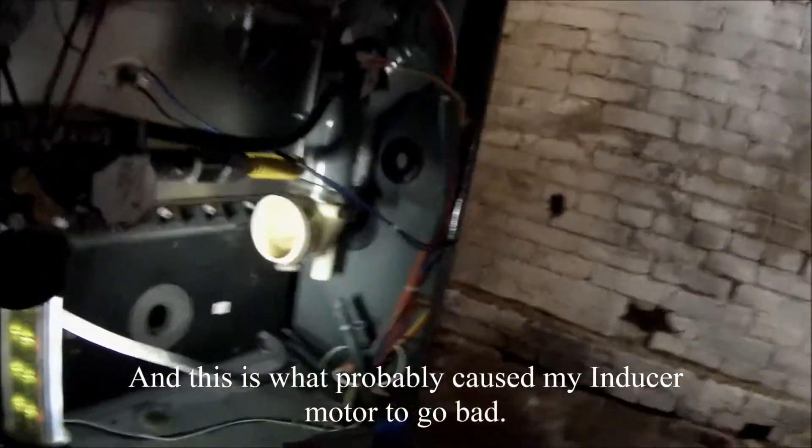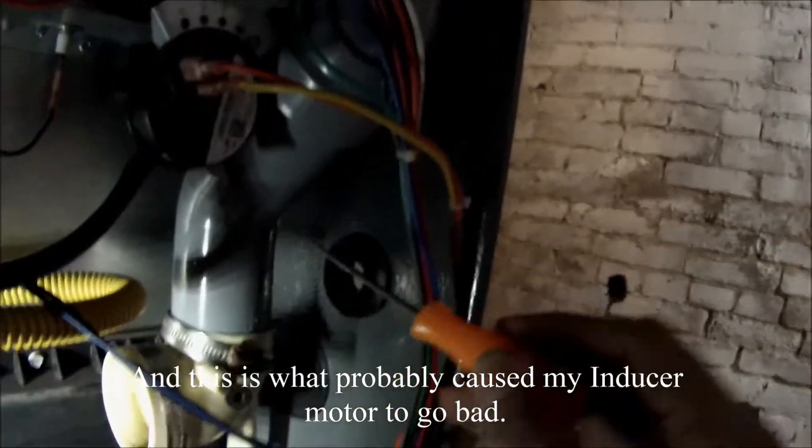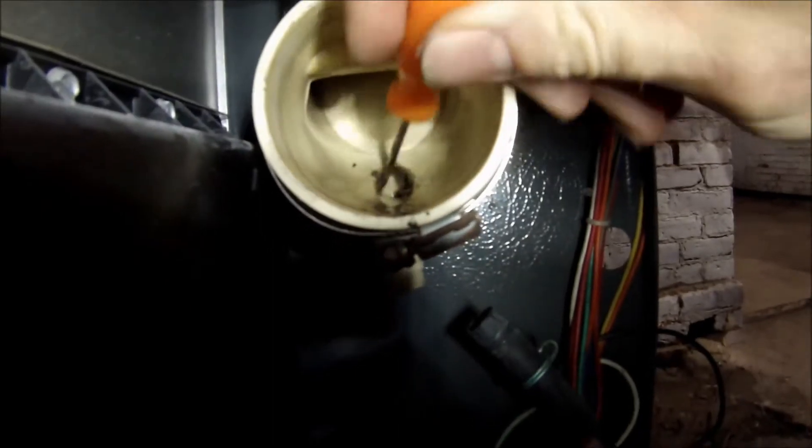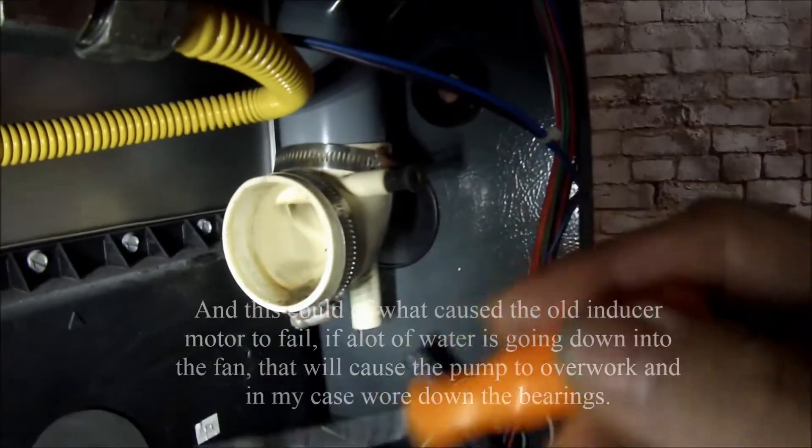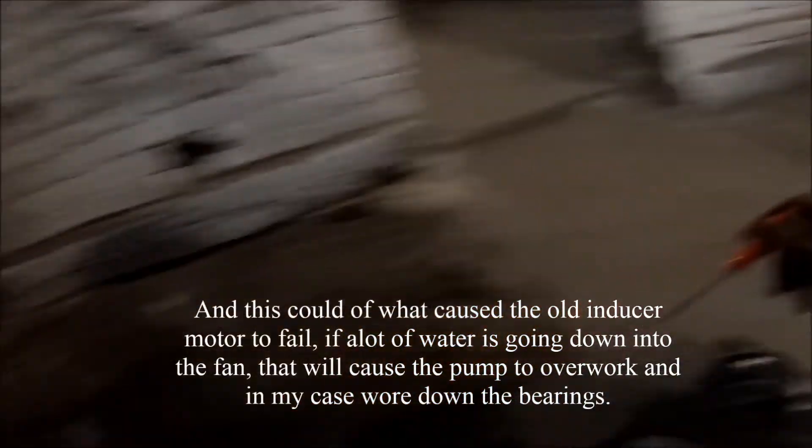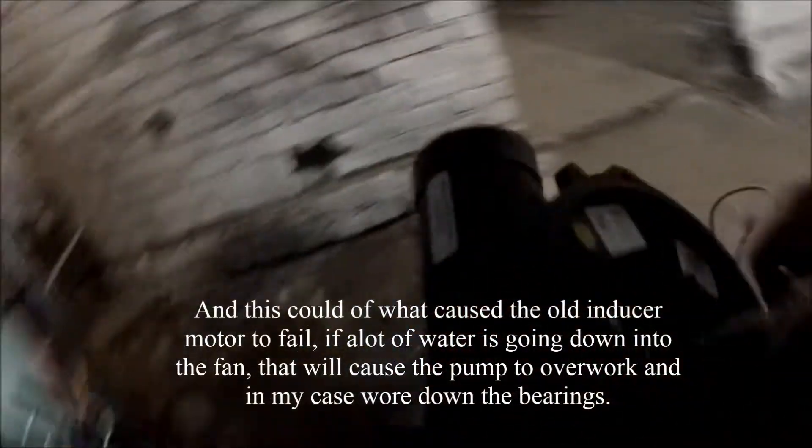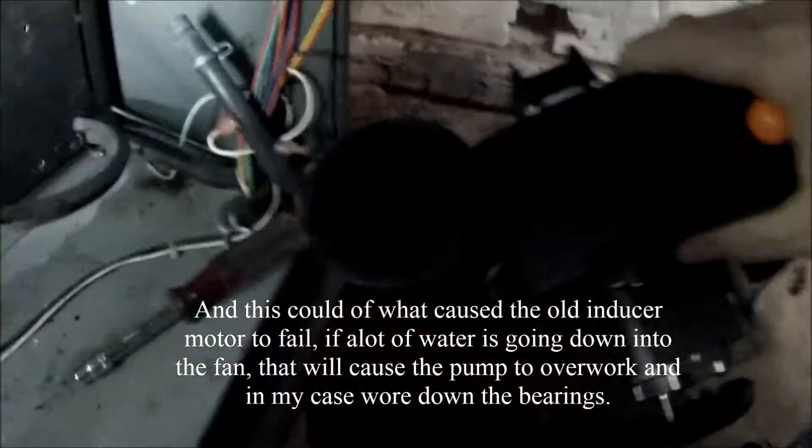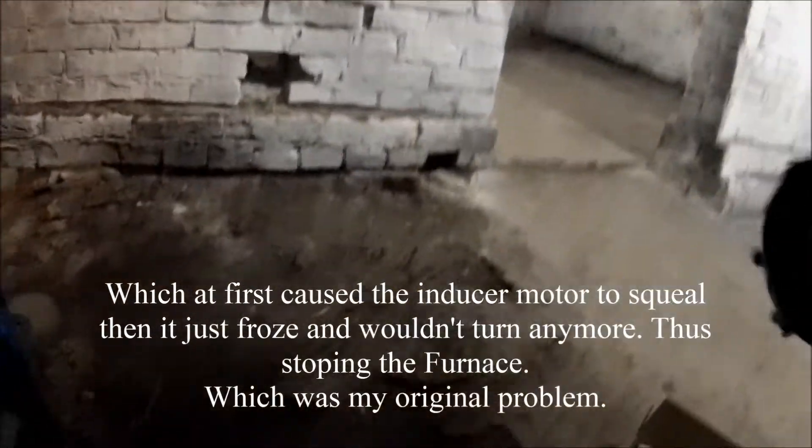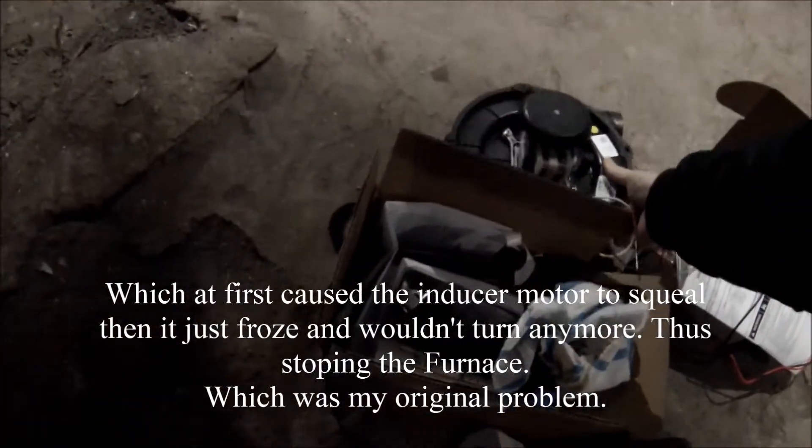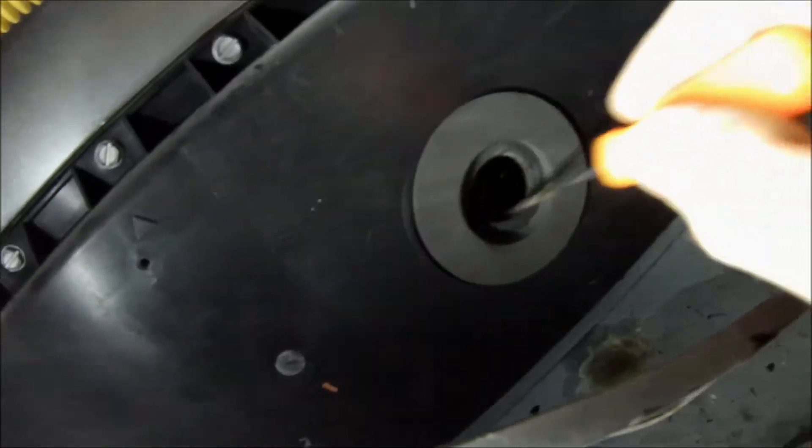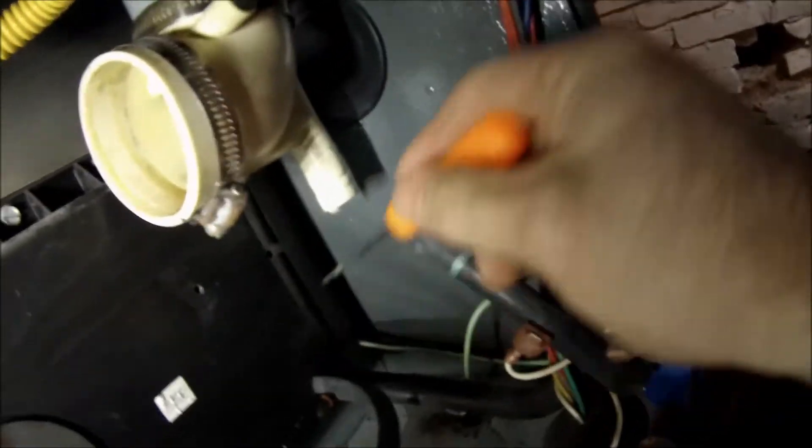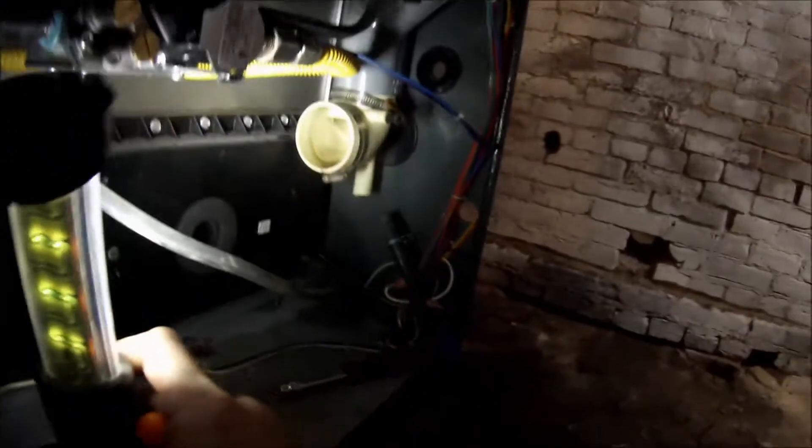And another thing I found is I pulled the, when I pulled the inducer out, I should have checked, but there's a little drain condensation, condensation drain that drips out right here. That thing was, let me see if you could see in there. That thing was really clogged up with hard water. So the water was dripping down this pipe going into my inducer motor. When I pulled the inducer motor out, it dripped a bunch of water from inside this inducer motor. So it was dripping into this pipe here. See, it's still wet in there a little bit and then getting into that, into the inside of it. And that ain't good because you're sucking all kinds of water. And not only is it sucking in there, it got in here into this hole. You don't want water in there. And then you have, you know, you got just a big mess of water leaking everywhere. And it wasn't leaking out to right here where it's going to flow, you know, put to a drain or whatever. So that was my issue. I'm pretty sure.